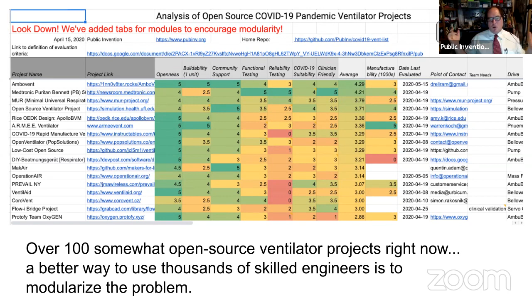We would modularize the problem. So Jenny and I came up with this basic modularization of a ventilator. The basic components are an air drive. That's what makes the air move. It could be a bag squeezer, a pump, a bellows, a fan, a pressure gating valve. The second module is a sensing module, which senses the pressure and flow in order to allow you alarming and monitoring to make sure that the ventilator is working correctly. In some designs, the sense module might feed data to the air drive to control it. That's not necessarily required, but it might be used in some cases.